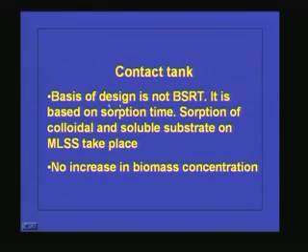So how can we design the contact tank? Contact tank design is not based on the BSRT, because we are not converting all the organic matter present in the system. It is based on sorption time, because whatever colloidal particles are present in the system, we want them to get attached to the microbial cells. So the adsorption process is more important in the contact tank than the biodegradation. So we have to design the system for that purpose. We know that adsorption is a very fast process, so the time required for adsorption is very less. That's why in the contact tank we give a contact time of only 30 minutes.